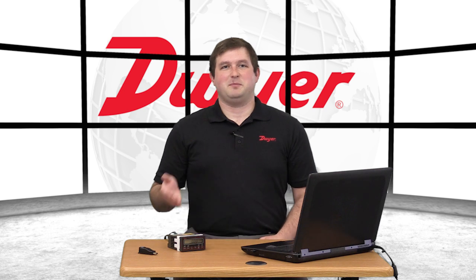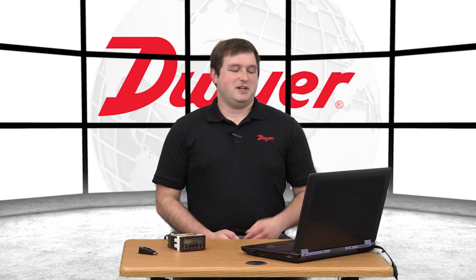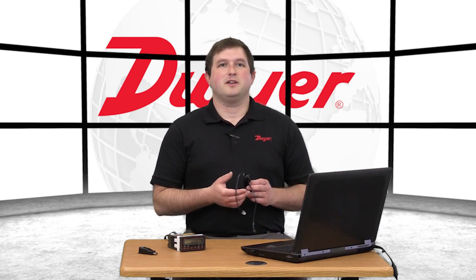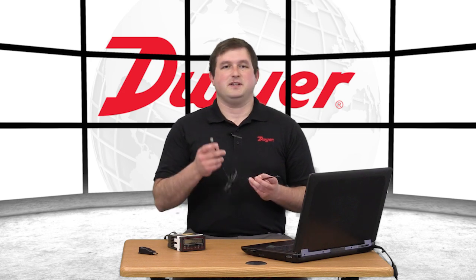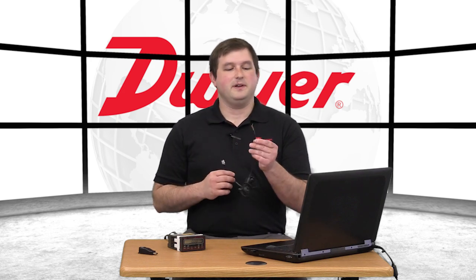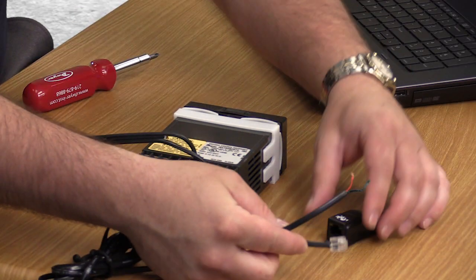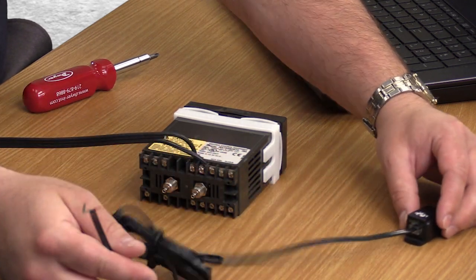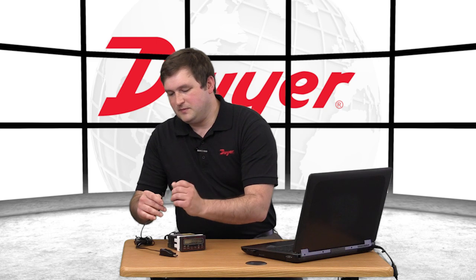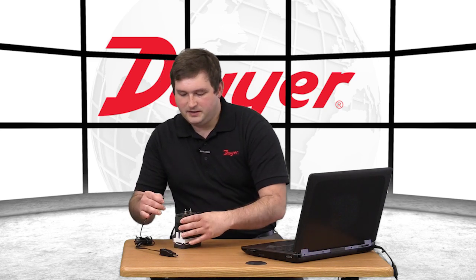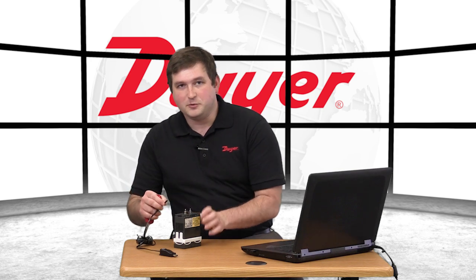To start, connect power to the DH. The MN-1 features a 2-wire communication cable that has an RJ45 connector on one end and strip leads on the other. Plug the RJ45 end into the mini node. The green wire is terminated on terminal 11 on the back of the DH and the red wire on terminal 12.